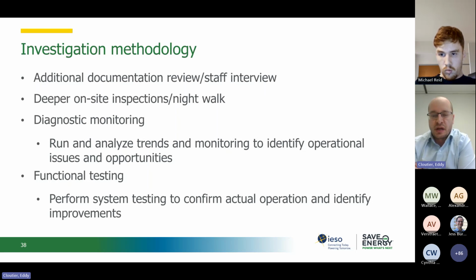So it's always a question of whether the sequence of operation and the outside air intake have been adapted to the new conditions. It's by analyzing the documentation and comparing it to the occupancy conditions that we are able to determine this. This is just an example of what analyzing documentation and comparing it with the actual operating conditions of the building can reveal as an improvement measure.